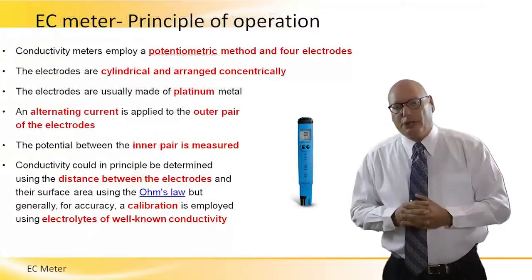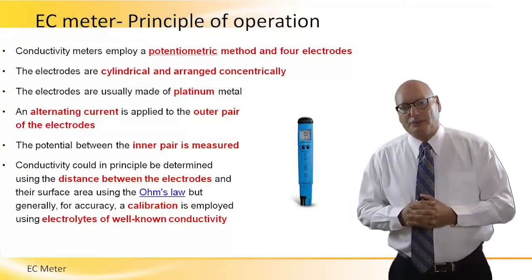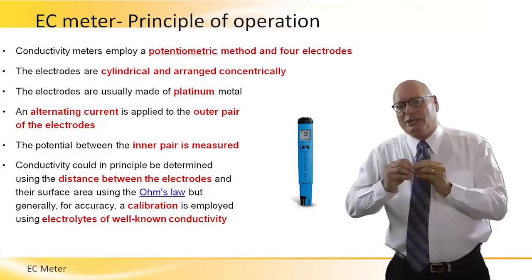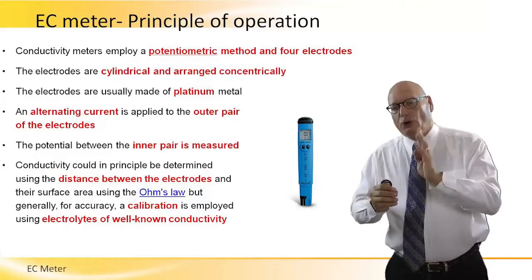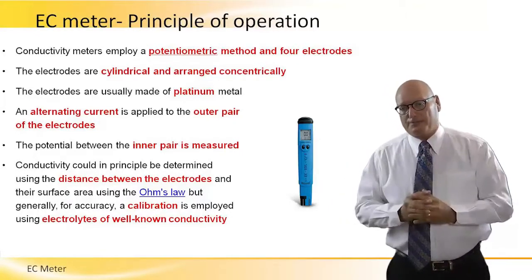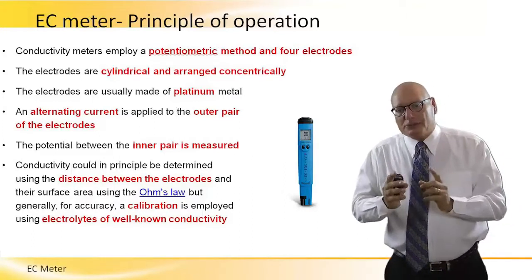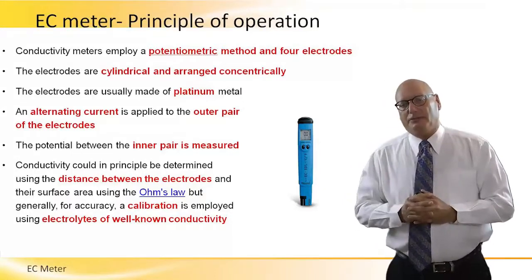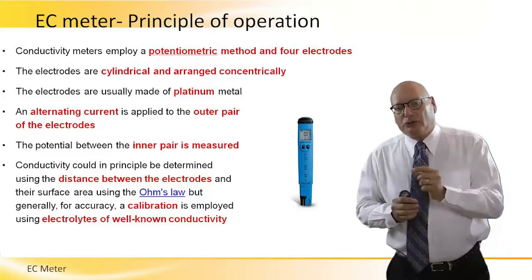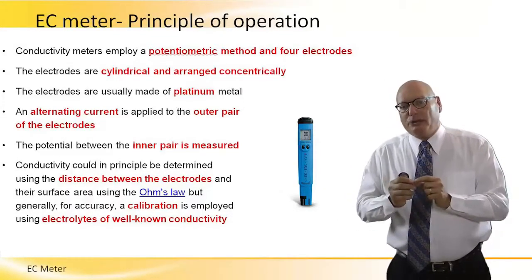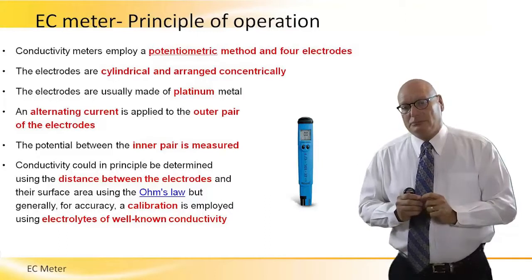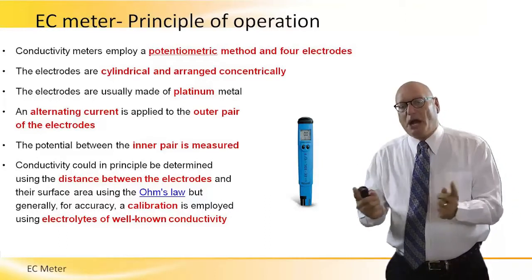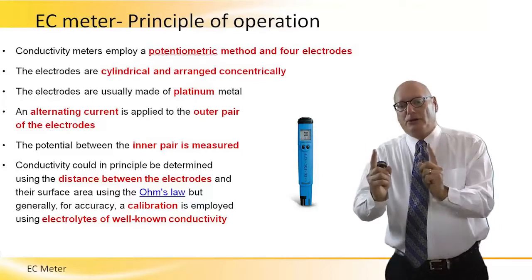The principle of operation is as such. Conductivity meters employ a potentiometric method and four electrodes. The electrodes are cylindrical and arranged concentrically, and are usually made of platinum. AC — alternating current — is applied to the outer pair of the electrodes.